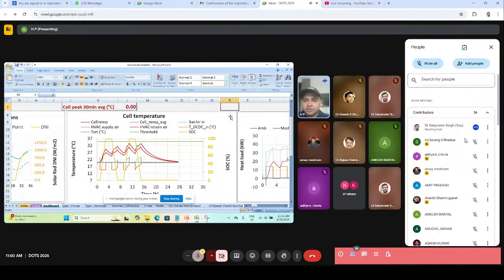We talk about air conditioner sizing of a room: you calculate the number of persons, number of heating components, calculate all the heat, and then say, okay, to dissipate that much heat, I need so much tonnage of the air conditioner. If you cool semiconductors or other electrical heating devices, you just need a number that, okay, I have X kilowatt being generated and I have to dissipate that. How effectively depends on the effectiveness of the cold plate or heat sink, and how much flow you have, those parameters come in. But in those applications, you just need that total heat generation number, and that gives you the ability to define your cooling capacity.